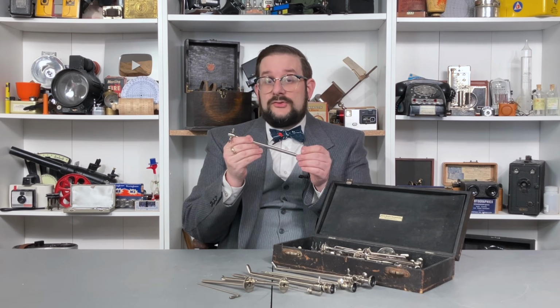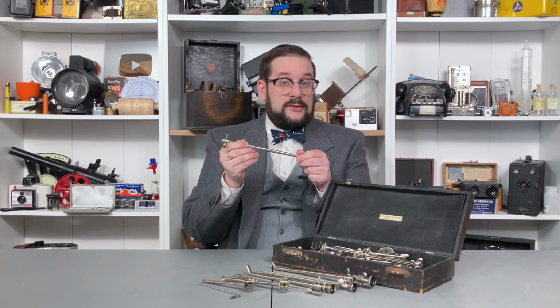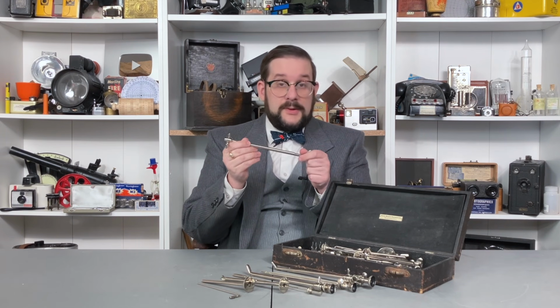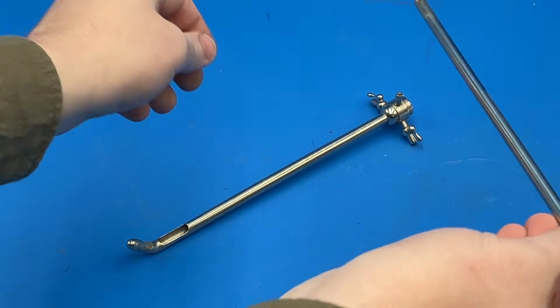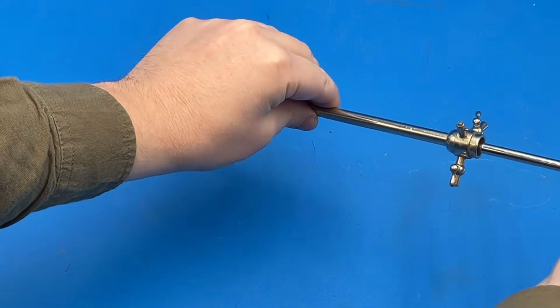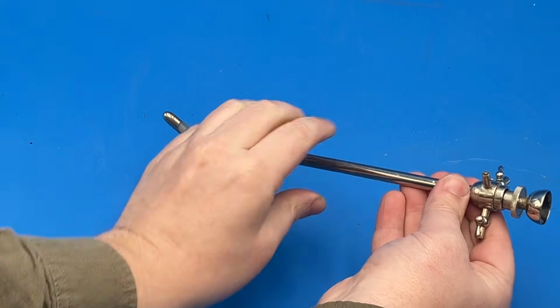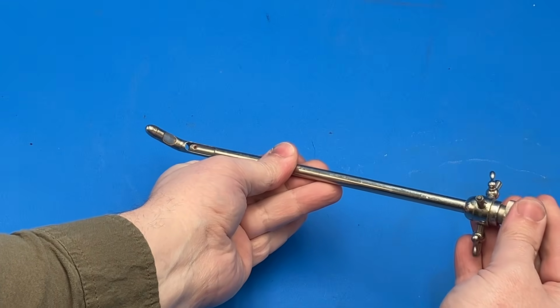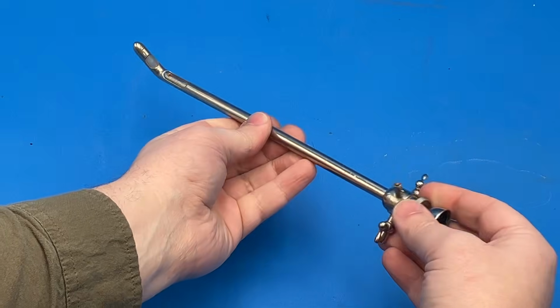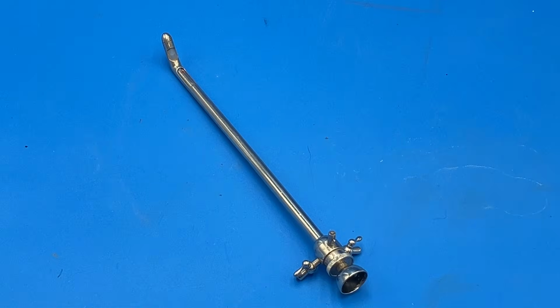While each of these instruments is designed to perform a particular set of procedures, they all share some common design elements. These are all so-called composite cystoscopes, comprising a separate hollow barrel or sheath into which various accessories can be inserted. This is in contrast to older-style fixed-lens cystoscopes, in which the lenses for observing the interior of the bladder were permanently integrated into the barrel.